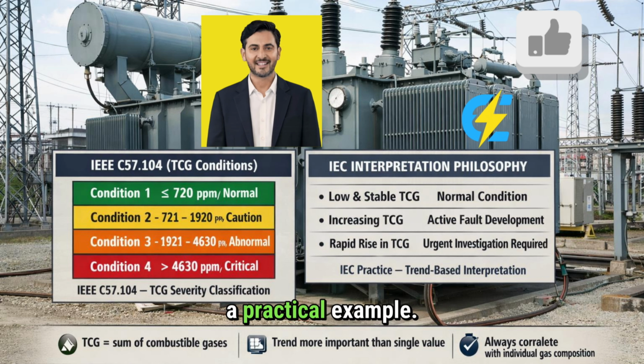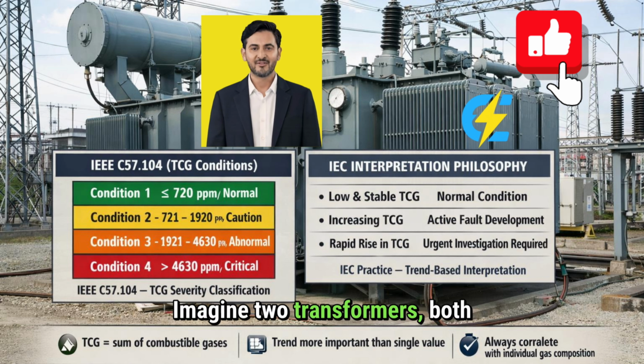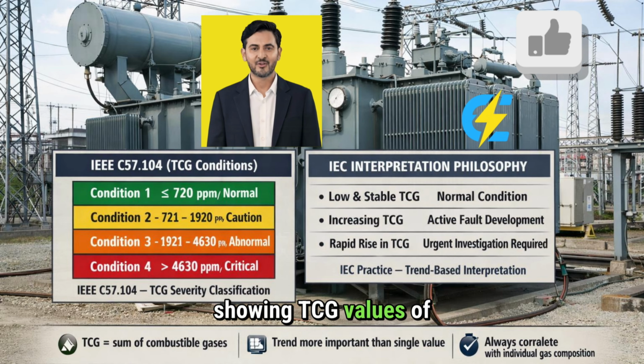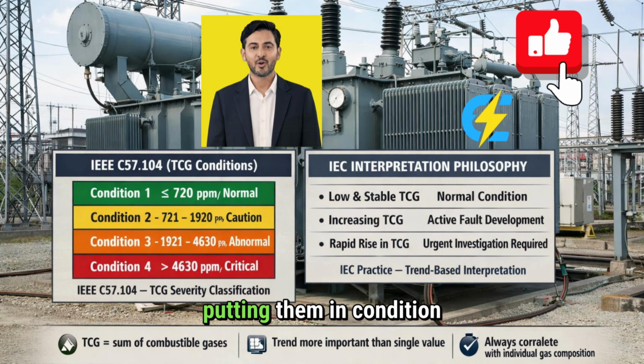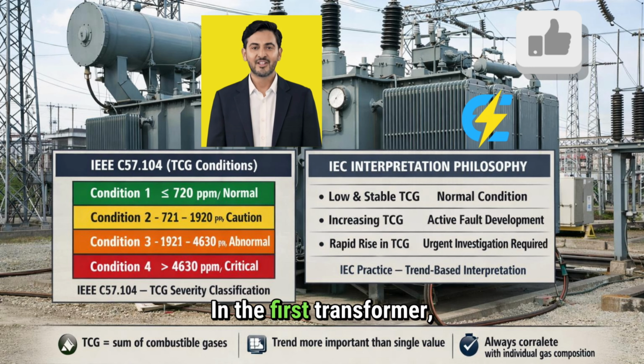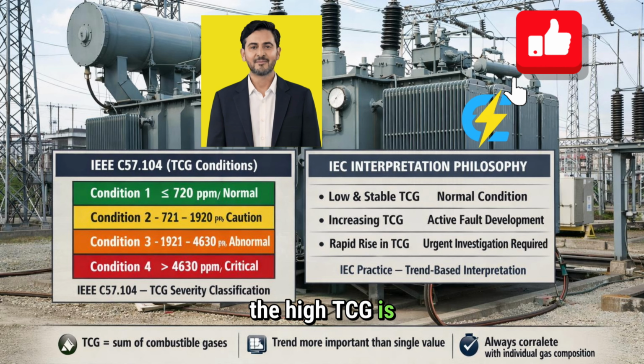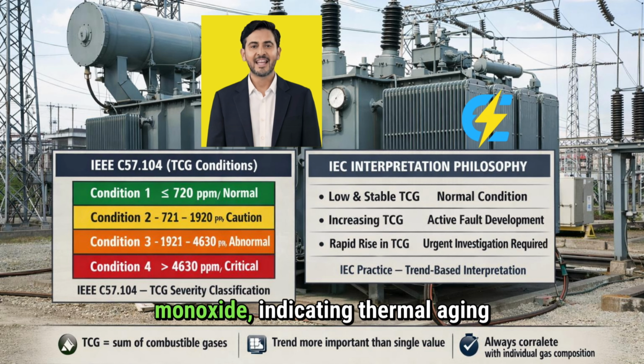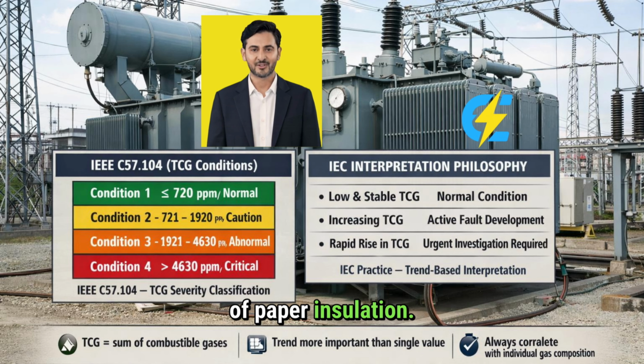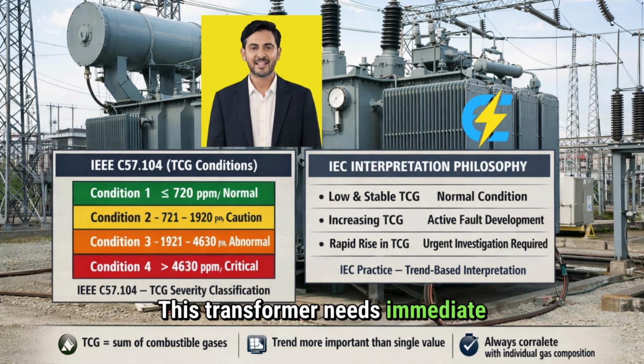Let me give you a practical example. Imagine two transformers, both showing TCG values of 3000 parts per million, putting them in condition 3. In the first transformer, the high TCG is primarily due to carbon monoxide, indicating thermal aging of paper insulation. This is serious, but manageable with proper load management and monitoring. In the second transformer, the high TCG is driven by acetylene, indicating arcing faults. This transformer needs immediate attention and possible emergency shutdown.